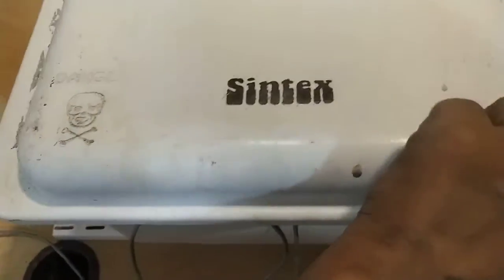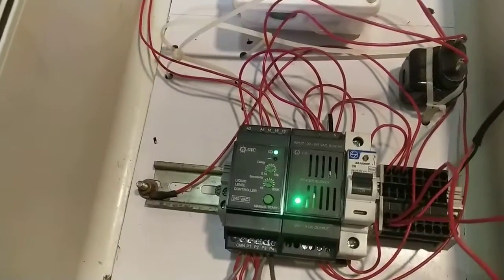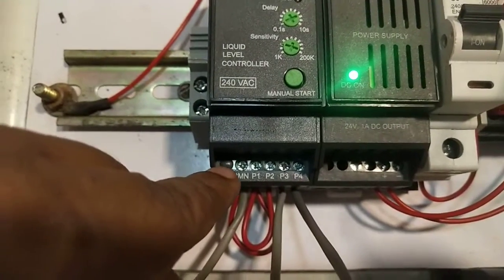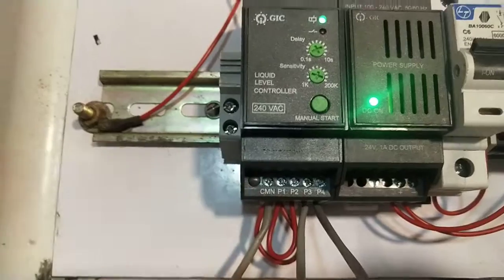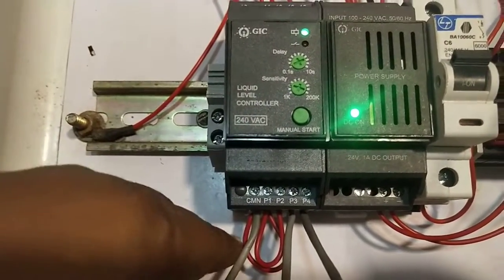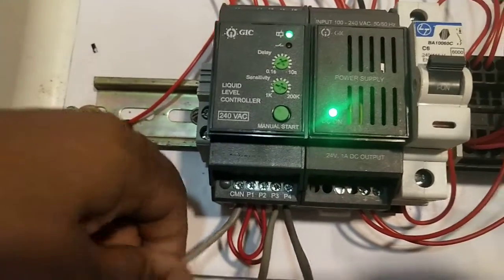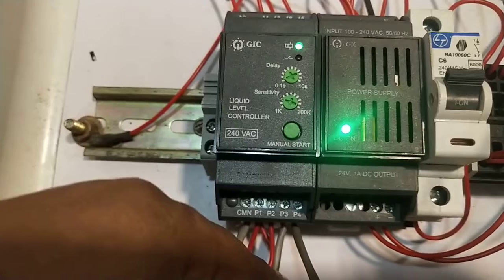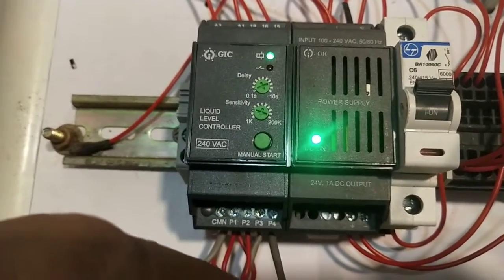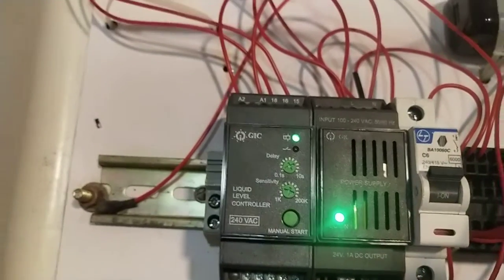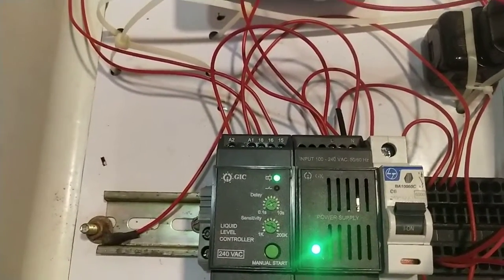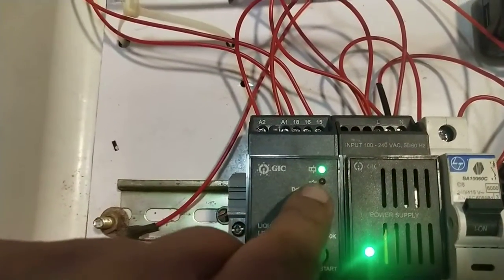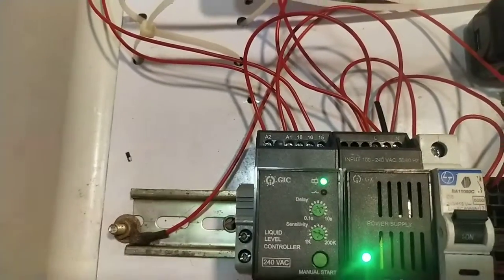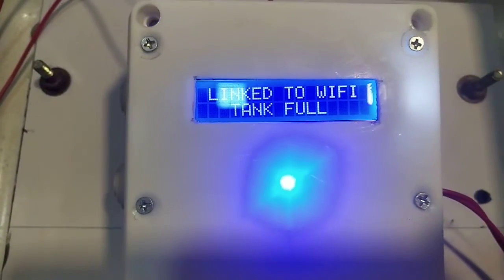Now these three probes are connected to this water level controller here of GIC make. The probe which is at the bottom, the reference probe, is connected to the common terminal. The low probe is connected to the P3 terminal, and the high probe is connected to the P4 terminal. Now since all the probes are immersed in water, this particular lamp, which indicates the relay output, is off, so the indication here is coming as tank full.